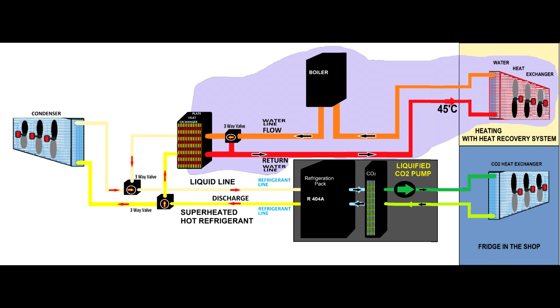It's obvious that there are many systems on the market, and this one has a boiler because it helps the heating process. But you can use this system without a boiler. However, if you decide to use this system without a boiler to control the heating agent temperature, you must have in the store another source of heat, because this is a heat recovering system. This is not a heater. This will not generate heat. This system will only recover heat.